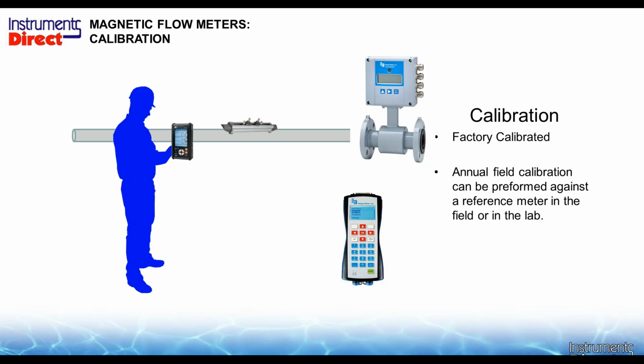Calibration. The mag meter comes ready to go, factory calibrated out the door. If you want an additional NIST certification, multiple point, that is an option, but the factory mag meter out the door is ready to go for most all installations. Should you have an application that requires a periodic or an annual inspection, there's a couple of different choices. One, say you're in the municipal market and you need to verify your flow meters once a year. You can pull the meter out of the line, which is not a lot of fun, send it back to us, and we can do an annual calibration.